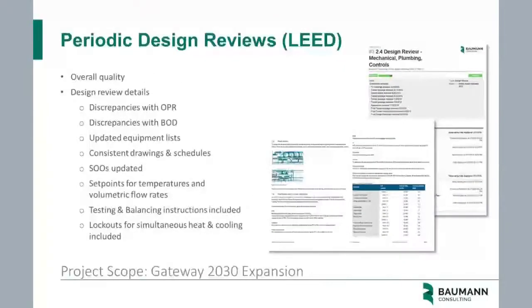We also performed periodic design reviews of the mechanical design documentation, shown in the center picture, to ascertain overall design quality and log any discrepancies with the OPR and BOD—owner project requirements and basis of design. We checked for updated equipment lists, sequence of operations, testing and balancing requirements, set points for temperatures and volumetric flow rates, including specified tolerances such as plus or minus 1 degree or a certain relative humidity requirement. Any discrepancies were logged on the CX web-based platform, documented to the right, and addressed during in-person and virtual meetings.